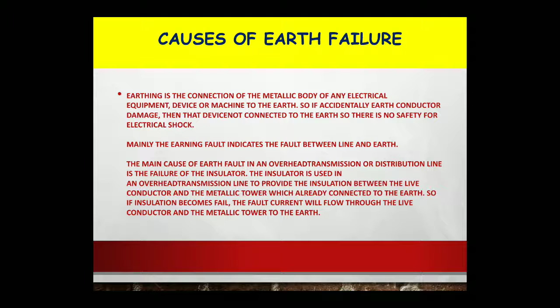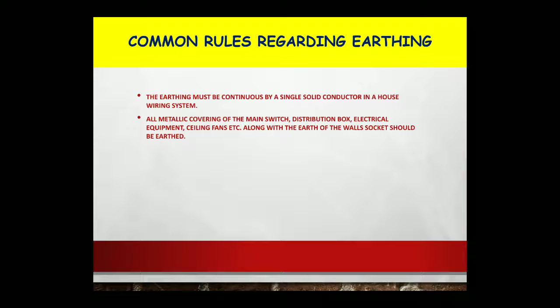And now the common rules regarding earthing. Number 1, the earthing must be continuous by a single solid conductor in a house wiring system. So no bunch or bundle conductor is used in case of earthing. Number 2, all metallic coverings of the main switch, distribution box, electrical equipment, ceiling fan, etc., along with the earth of the wall socket should be earthed. Number 3, the resistance of the earth continuity conductor should not be more than 1 ohm throughout the system. So the maximum resistance of the earth conductor is 1 ohm.